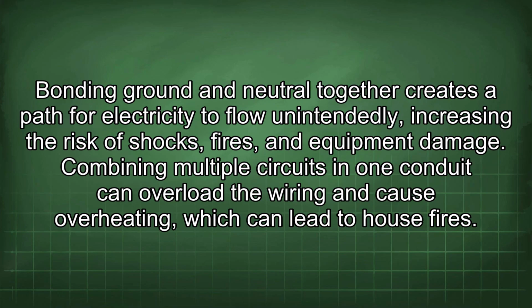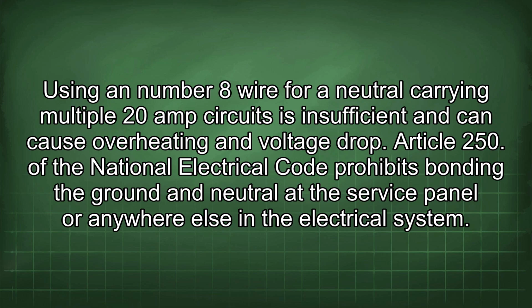Bonding ground and neutral together creates a path for electricity to flow unintendedly, increasing the risk of shocks, fires, and equipment damage. Combining multiple circuits in one conduit can overload the wiring and cause overheating, which can lead to house fires. Using a number 8 wire for a neutral carrying multiple 20-amp circuits is insufficient and can cause overheating and voltage drop.